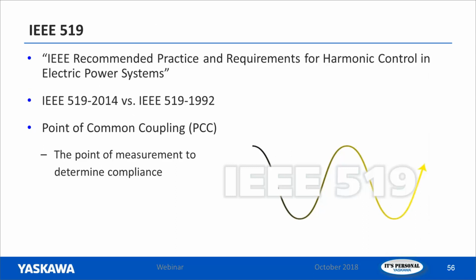So IEEE 519, what is it? IEEE recommended practice and requirements for harmonic control in electric power systems. IEEE had to come up with a standard to try to control the amount of harmonic distortion that's acceptable. So they came out with this standard in 1992, but since then it did get revised in 2014. The major difference between these two standards, I mean the most relevant, is going to be the point of common coupling, which is the PCC, and that's the point at which you take your measurements to determine whether or not you're in compliance with IEEE 519.